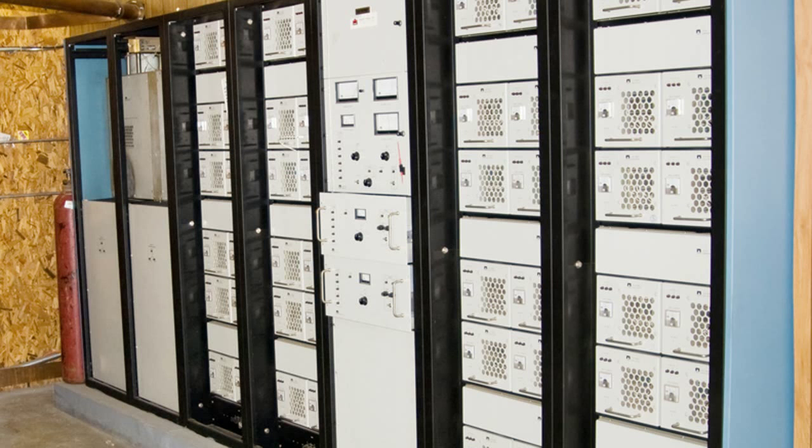So you can see what it looks like and what we have to do to get it back 100%. There are two three-phase power supplies powering this station, and they're all the way toward the back. The one that has the problem is this one — it's the one on the right side. So we need to remove that panel and the corresponding panel in the back.